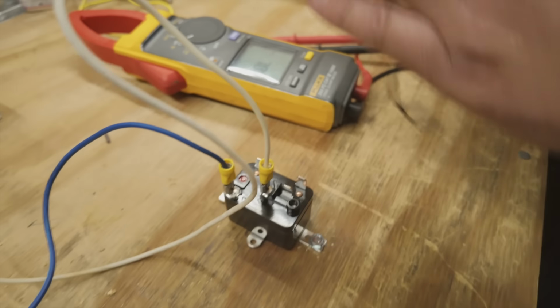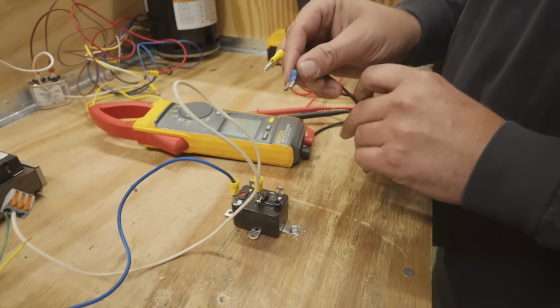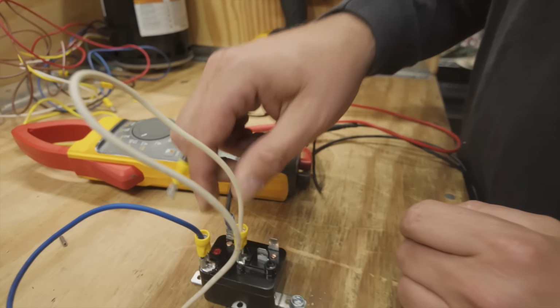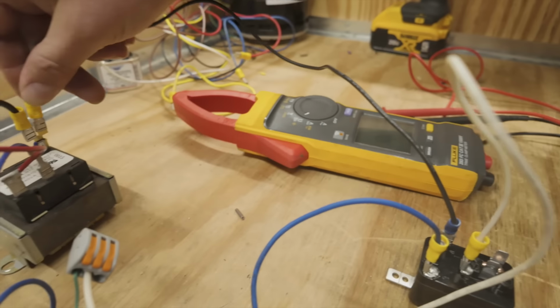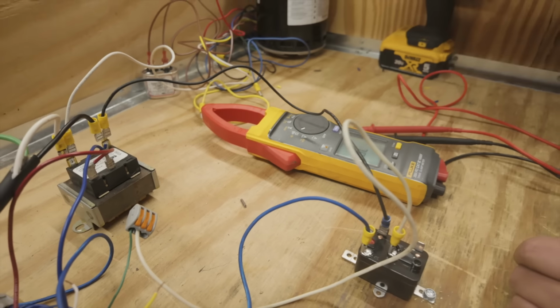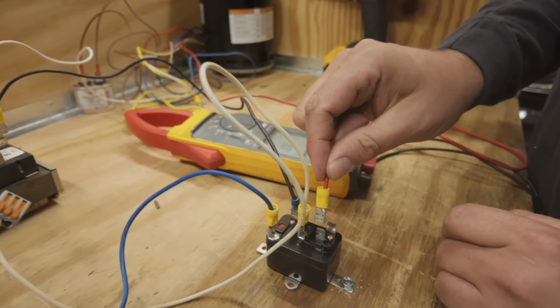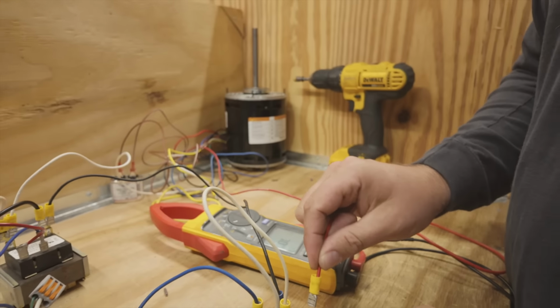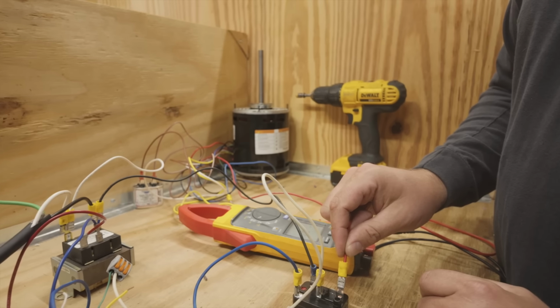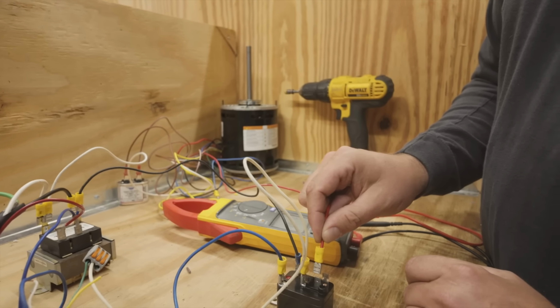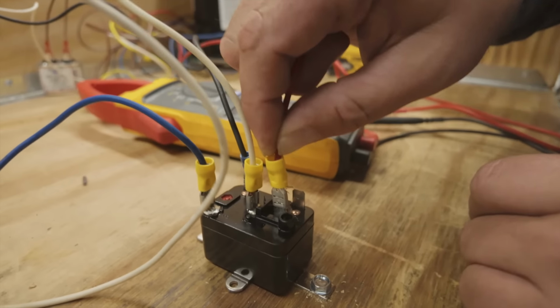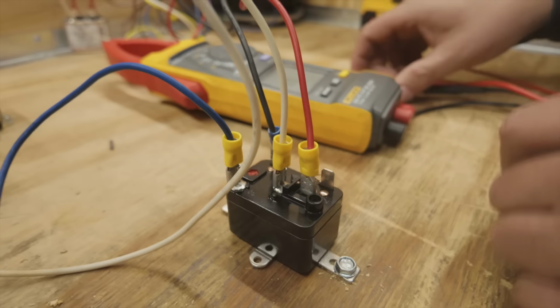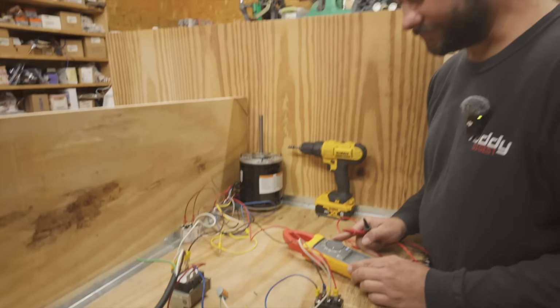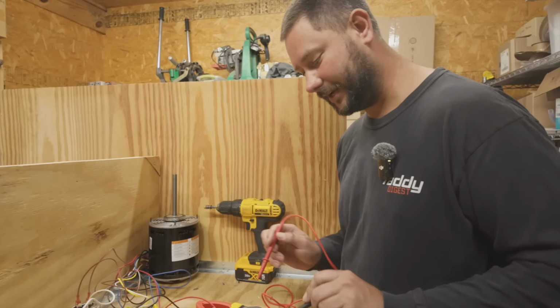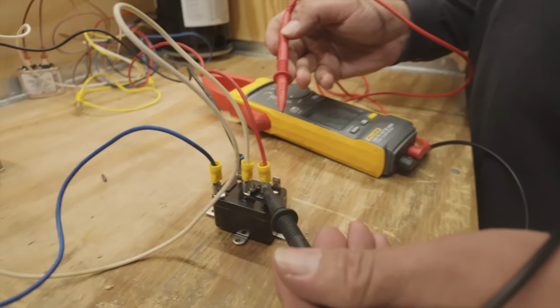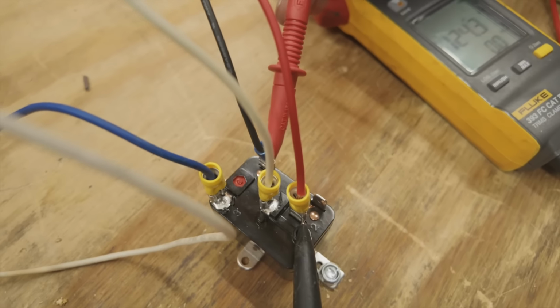All right, so we got to get our power coming in first. One side of the line. And then we'll use our low speed for our motor. If we connect it here, watch. Fan motor kicks on, right? Normally closed. Let's go to the normally open contact. It doesn't kick on. Now, if we check volts AC, let's do this again. Here we go.